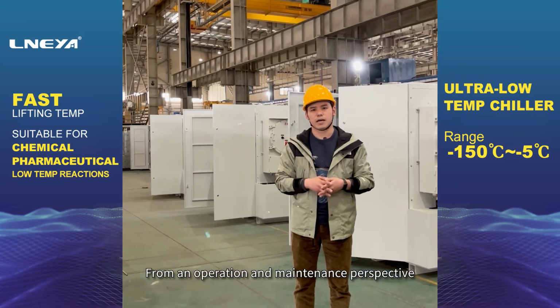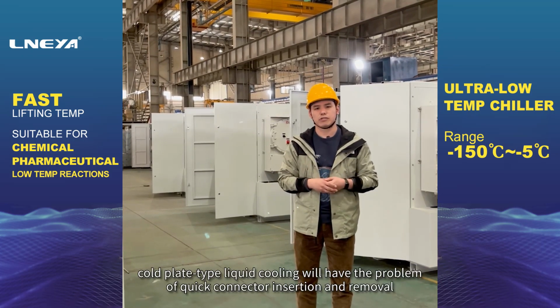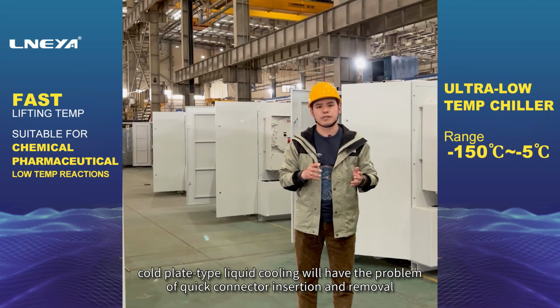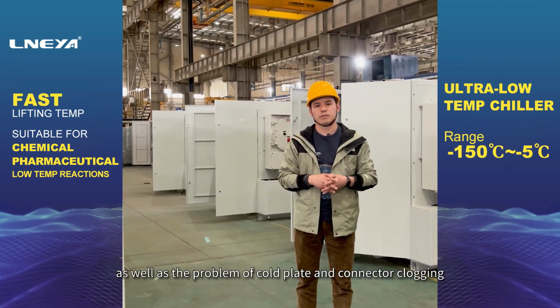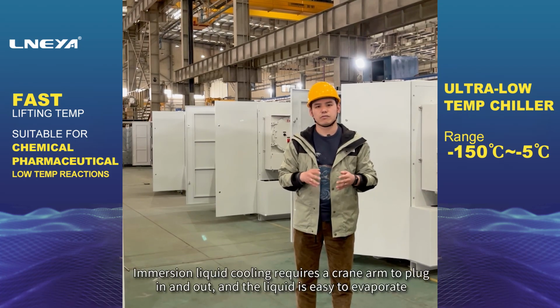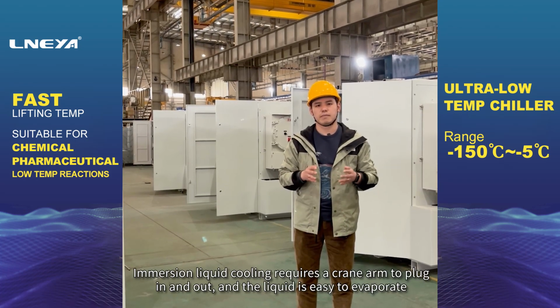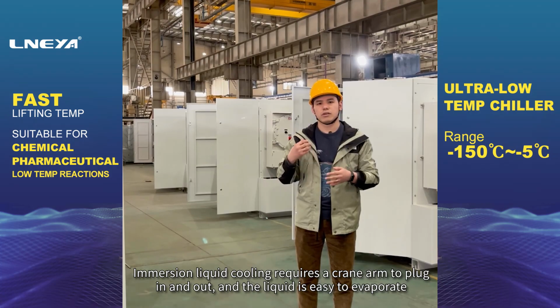From an operation and maintenance perspective, cold plate liquid cooling will have the problem of quick connector insertion and removal, as well as the problem of cold plate and connector clogging. Immersion liquid cooling requires a crane arm to plug in and out, and the liquid is easy to evaporate.